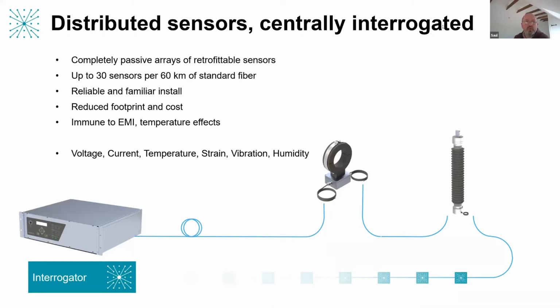You no longer require power supplies, copper wiring, GPS clocks at these locations to timestamp. You don't require any form of digitalization using multiplexers or merging units, and you don't require a data network to bring that signal back. Everything is connected through coded light from a remote point. That's why we can go so far out and measure simultaneously and permanently so many locations at very high levels of accuracy. Also worth noting, we have already marinized this technology.